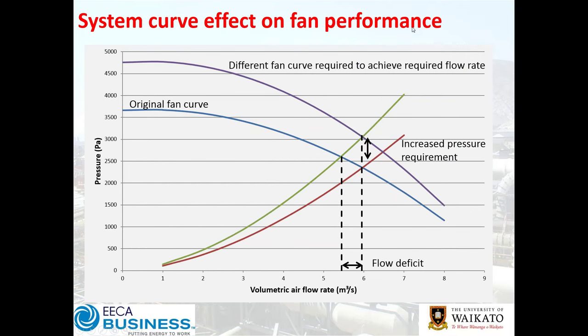Is this just theoretical, or does it really matter? Looking at our fan curve and system curve plot: if we have our design system curve in maroon and the actual system curve in green, with a required flow rate of six cubic metres a second, what happens is — with a higher actual system curve at a fixed fan speed — the actual flow delivered will be somewhat less, sitting around five and a half.